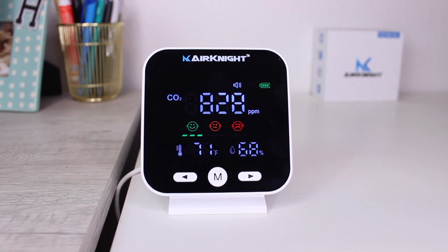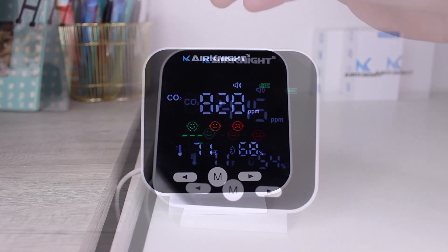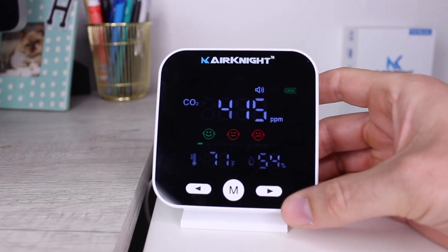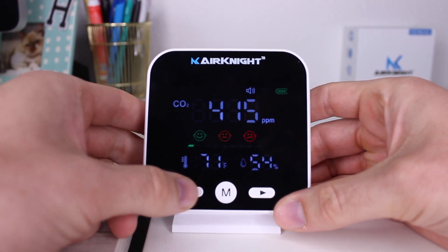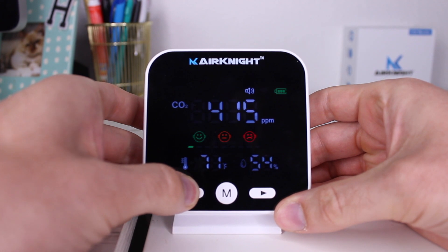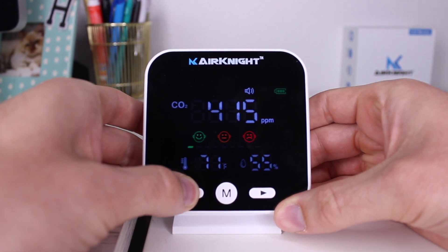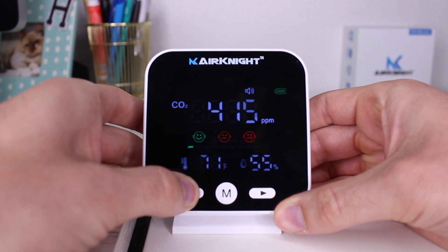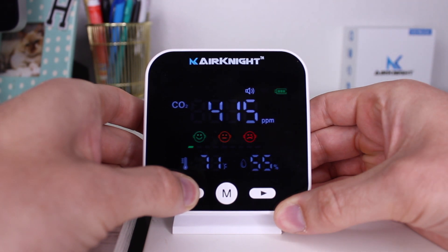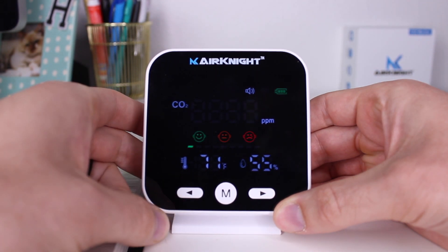Once the reading is at or close to the 413 reading, press and hold the left button for 5 to 10 seconds until you hear a beep sound and the CO2 value starts flashing.